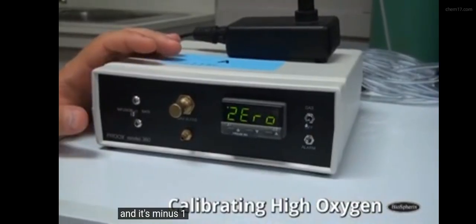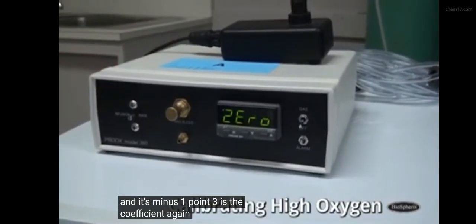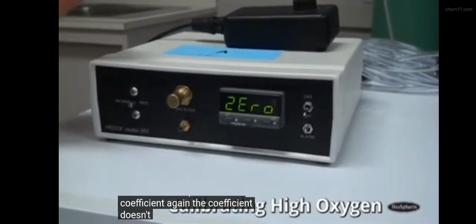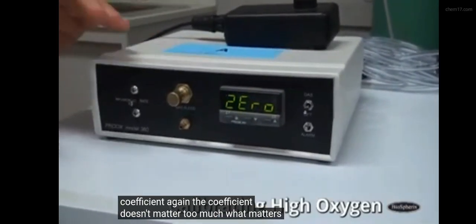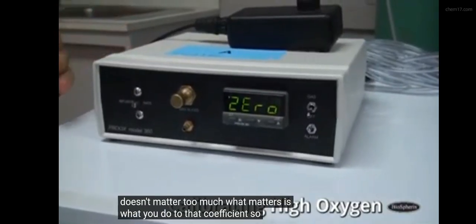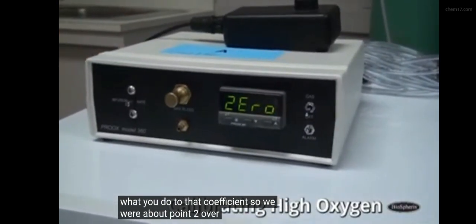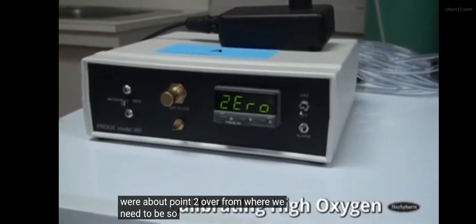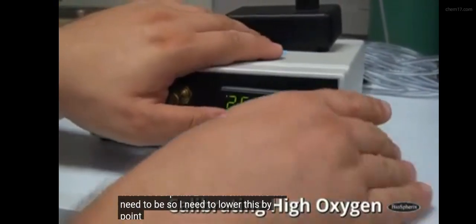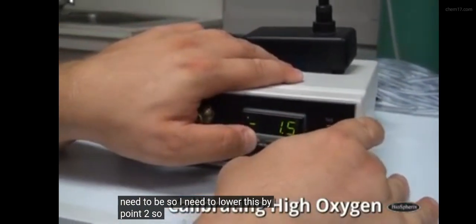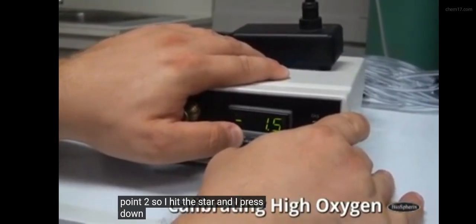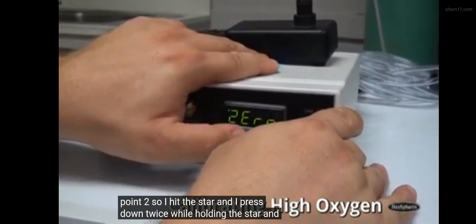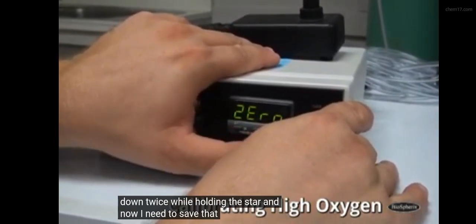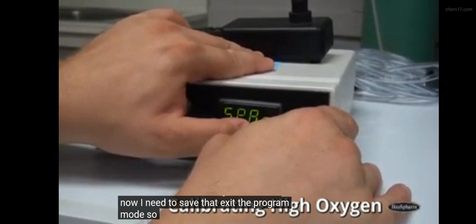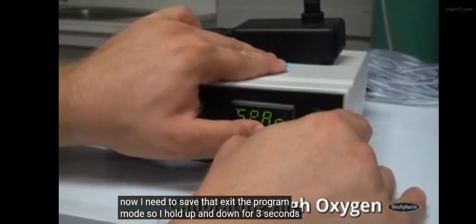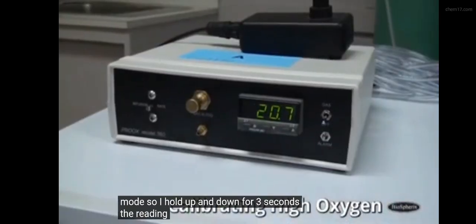And it's minus 1.3 is the coefficient. Again, the coefficient doesn't matter too much. What matters is what you do to that coefficient. So we were about 0.2 over from where we need to be, so I need to lower this by 0.2. So I hit the star and I press down twice while holding the star. And now I need to save that and exit the program mode, so I hold up and down for 3 seconds. And then the reading comes back.